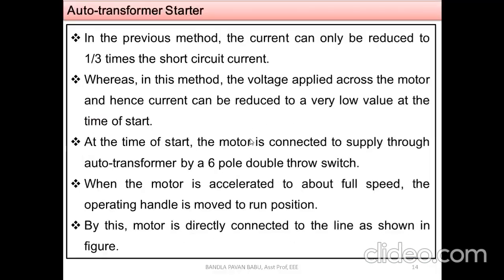Whereas in this method, the voltage is applied across the motor, and hence the current can be reduced to a very low value at the time of start. Let us see how we apply the voltage and reduce the current. At the time of start, the motor is connected to the supply through an auto transformer by a 6-pole double throw switch, which is nothing but a changeover switch. When the motor has accelerated to about full speed, the operating handle is moved to the run position.